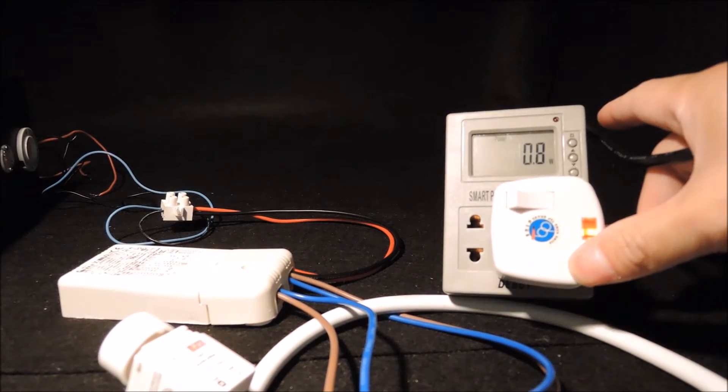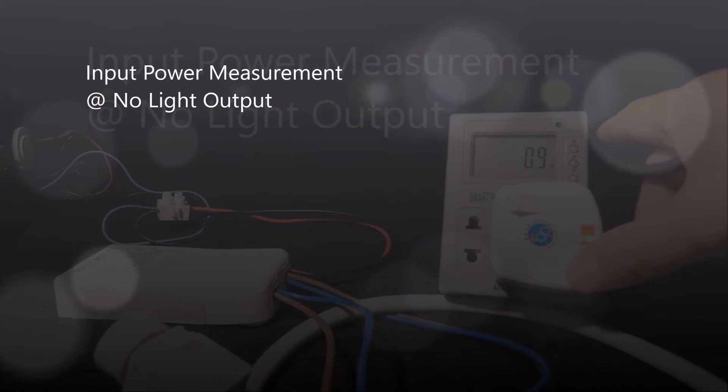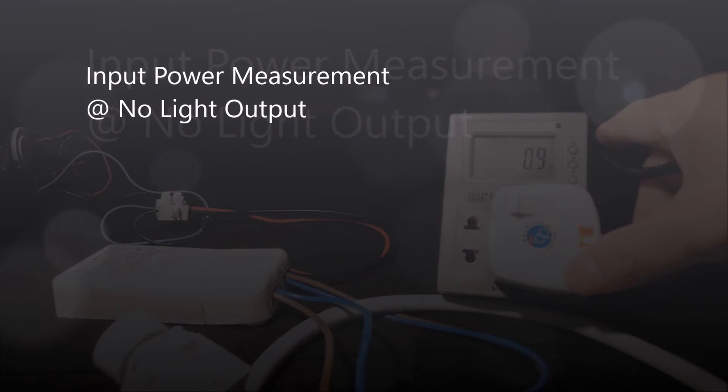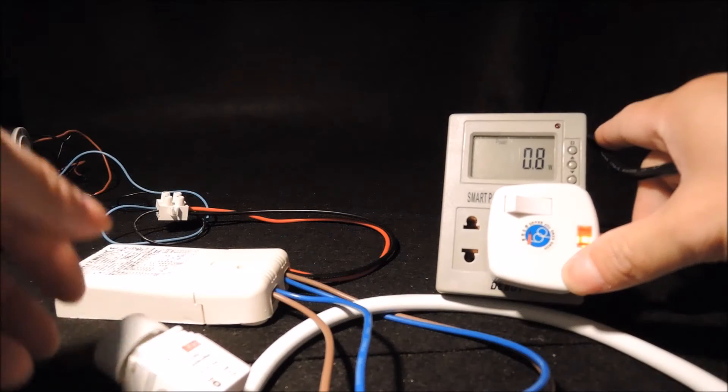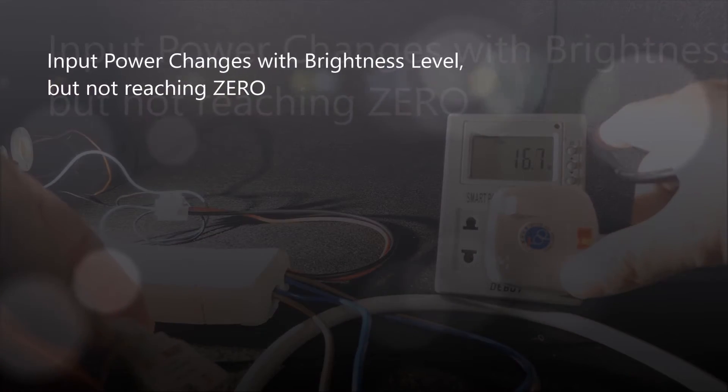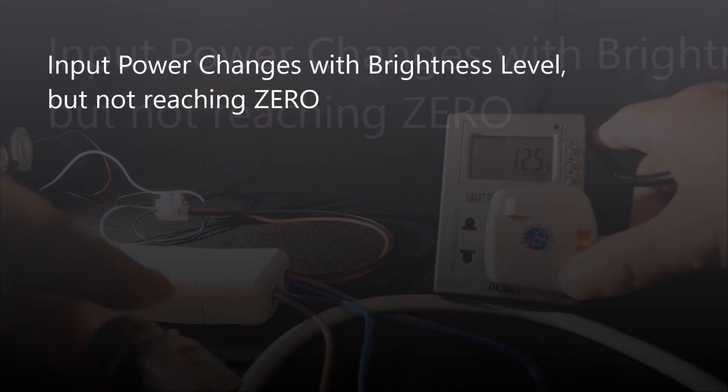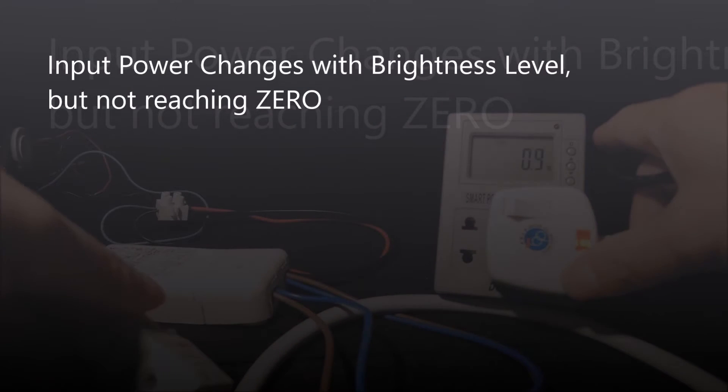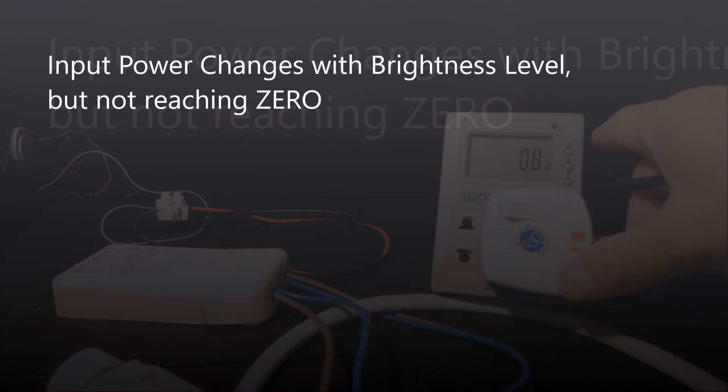Interestingly, although we don't see any light output from the power meter, you'll see there's still a certain level of power consumption here. The input power definitely changes with the dimming or the brightness level, but it would not reach zero even when we see no light output.